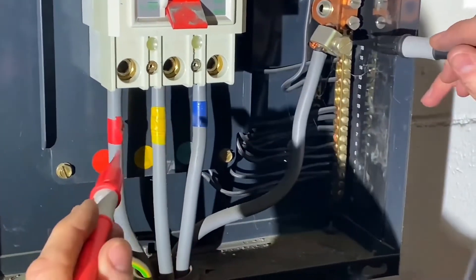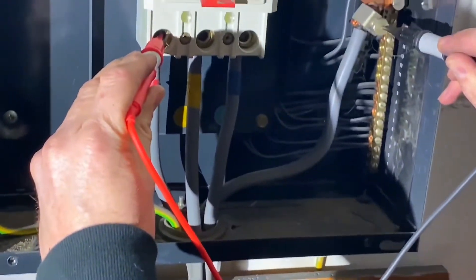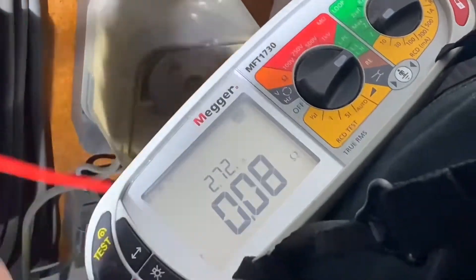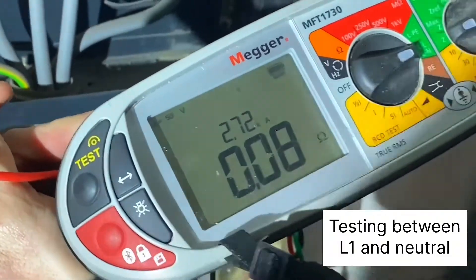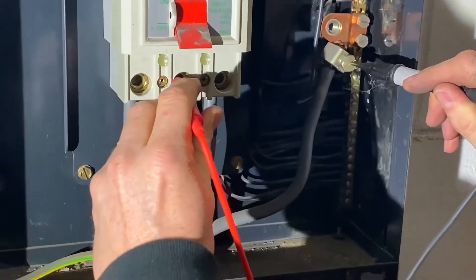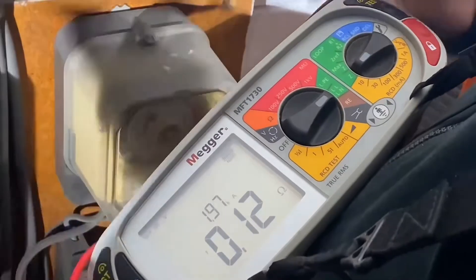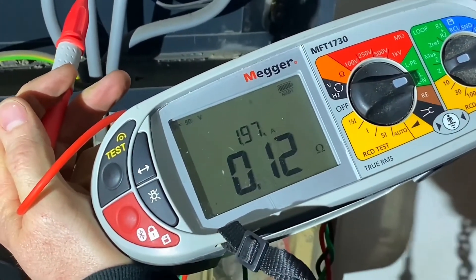So we're just going to probe onto the neutral conductor and then onto the line conductor, and again you can see it's picked up a voltage there. Voltage first, then we come back - it should come through a little quicker. So that's 272 amps. That's phase one, so we'll make a note of that. We'll go on to phase two. That's 197 amps.